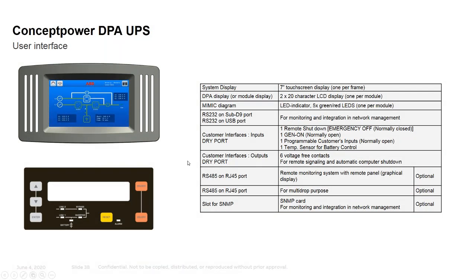And then just a few general comments on monitoring and communication. Like all UPSs, they have a color touchscreen display on the front, across the board, all of them. The reason for this, and this slide is from the modular system, is that the little one shown at the bottom here is to illustrate that each power module in the modular products actually has its own display as well. So there's redundancy on the power modules. If a power module should go bad, the remaining modules can support the load no problem.